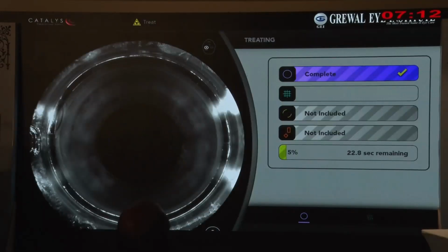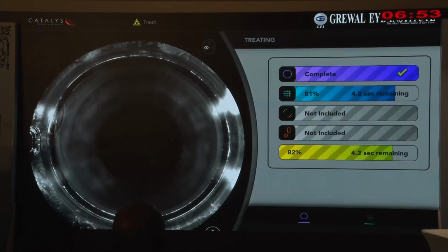This is again another case, and the settings of the Catalys again are set for a hard cataract. You can make the capsulotomy 5.5. Normally we'll keep it at 5.1. You have a higher number of passes, you increase the energy, and have a shorter spacing between them. And since you are doing 5 passes, it is going to take a little longer.